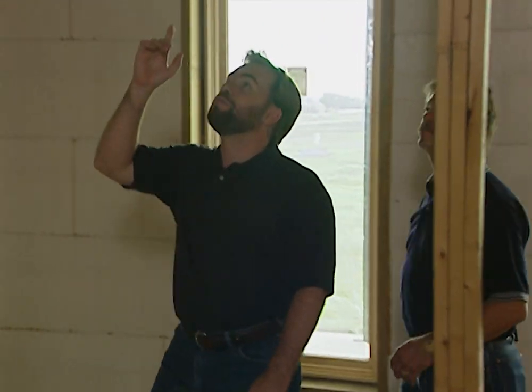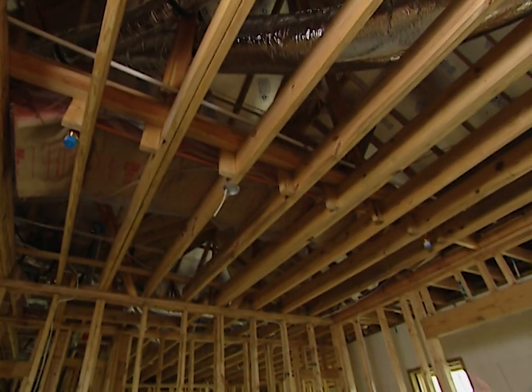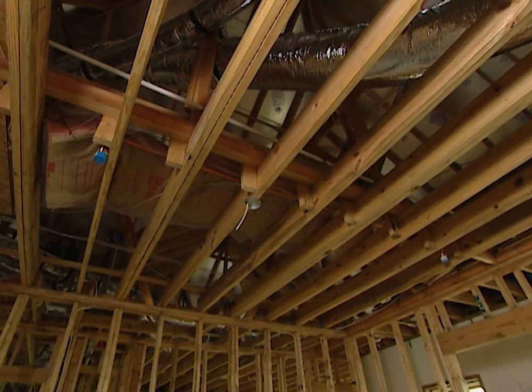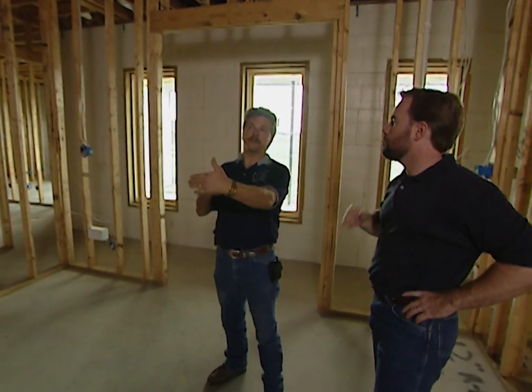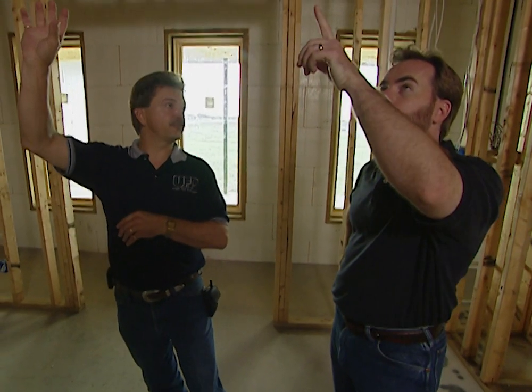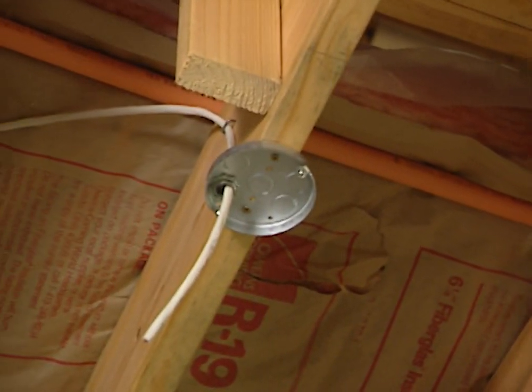Okay, Gary, I can follow the pipe. Then I see inside this room you've actually got 2 places for sprinkler heads to be attached. How come 2 instead of 1? Well, in this room, Michael, it's a 16-foot by 14-foot room, which only requires 1 sprinkler, with the exception that we have a ceiling obstruction by the light fixture in the center of the room. It forms an obstruction to our spray pattern, which means that now we have to split those up and have 2 sprinklers. And how much area will a sprinkler cover? They're designed generally for a 16 by 16 foot spray pattern, meaning you can be 8 foot off of any 2 walls, or a maximum of 8 foot. So we could have done one, like you said, if the light wasn't right there in the center of the room.